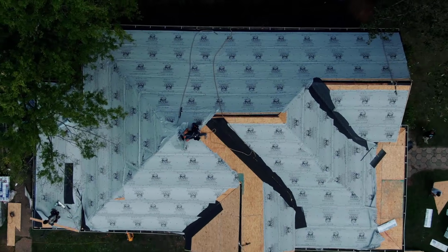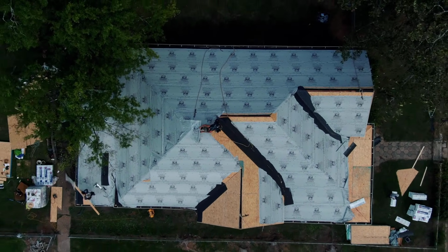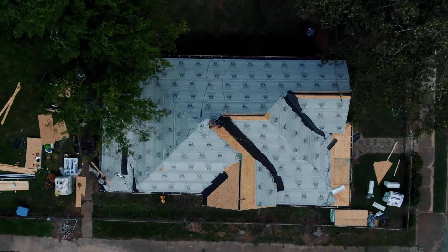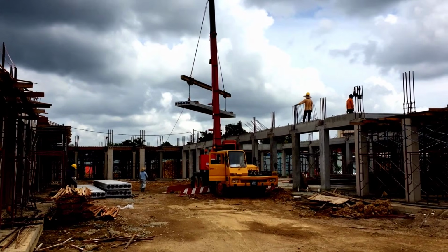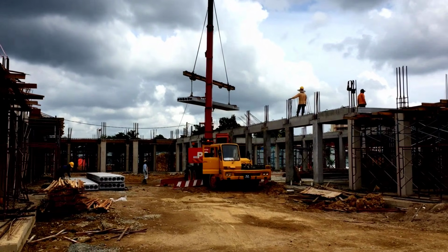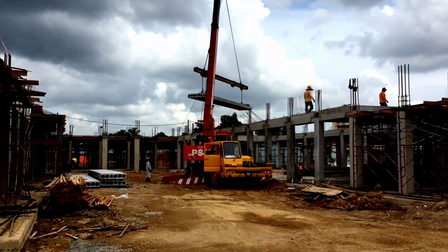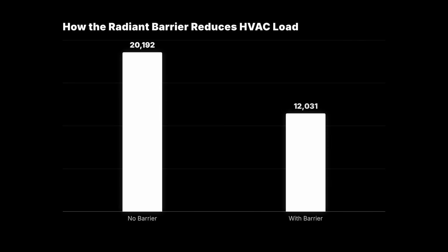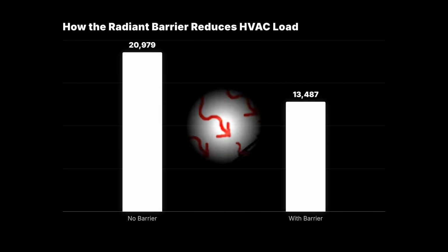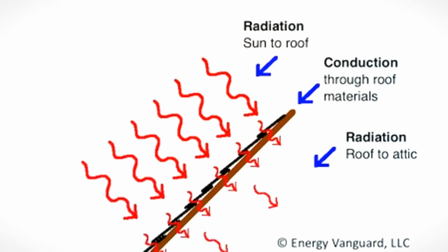Now here's where the $12,000 actually comes from, and I want to walk through this honestly instead of just throwing the number at you. This isn't the radiant barrier saving you money directly at the checkout counter. It's the radiant barrier changing the input numbers on your manual J calculation, enough that your HVAC contractor can legitimately spec a smaller system instead of an oversized one.